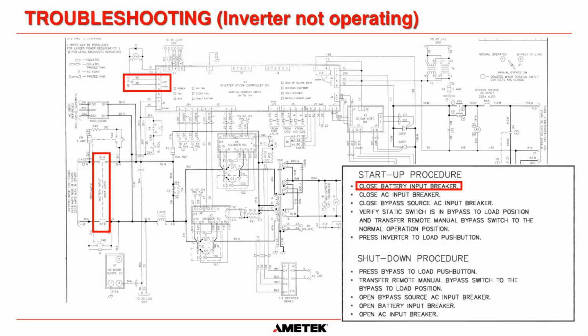So if there's something wrong with the auxiliary contact in B1, which can happen, it doesn't matter if your DC is good and everything else is good. If this contact does not close, the inverter will never, ever start. So if you have a little bit of troubleshooting skills and you think that maybe the B1 aux contact is bad, if you have a way to jumper across 3 and 4, you can see if you can get that system to start and basically disable the B1 aux contact. Obviously, you will need a new B1 aux contact, and you need to order that from us, but it's a good way to check why the inverter isn't starting. It could be that B1 aux.